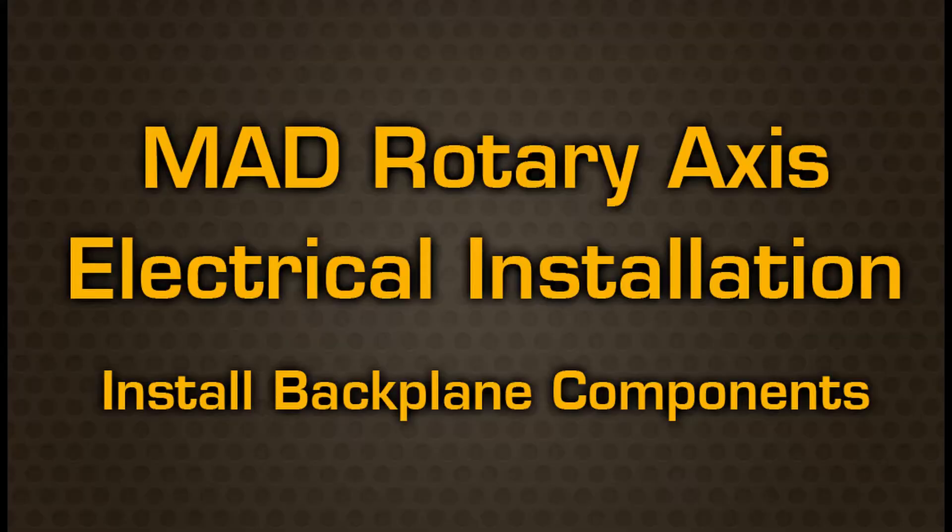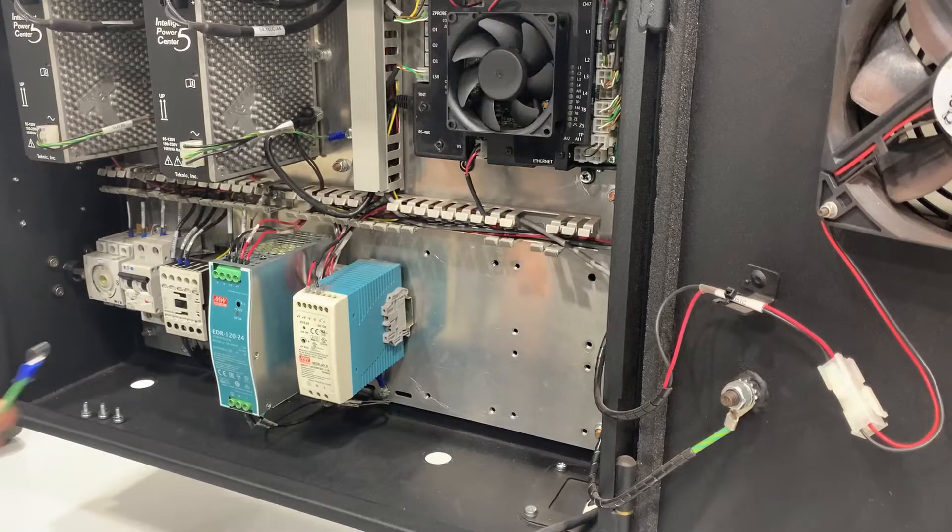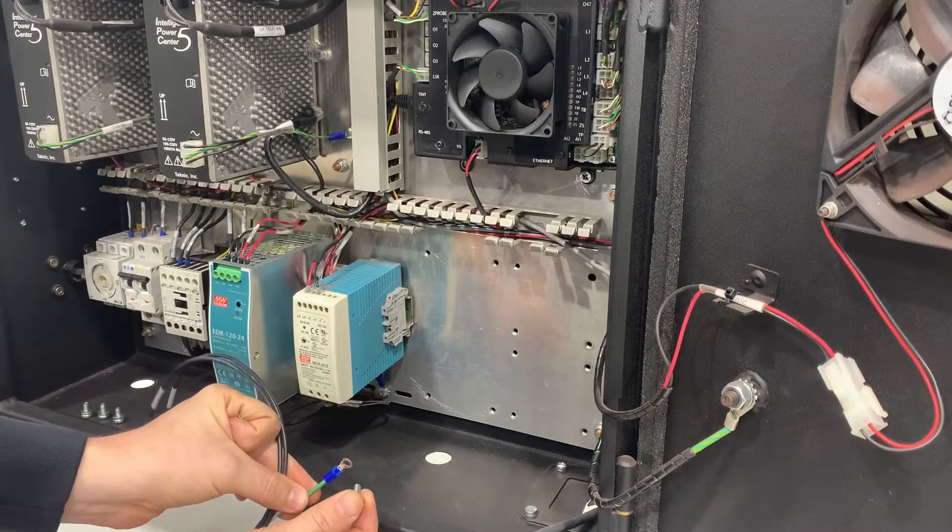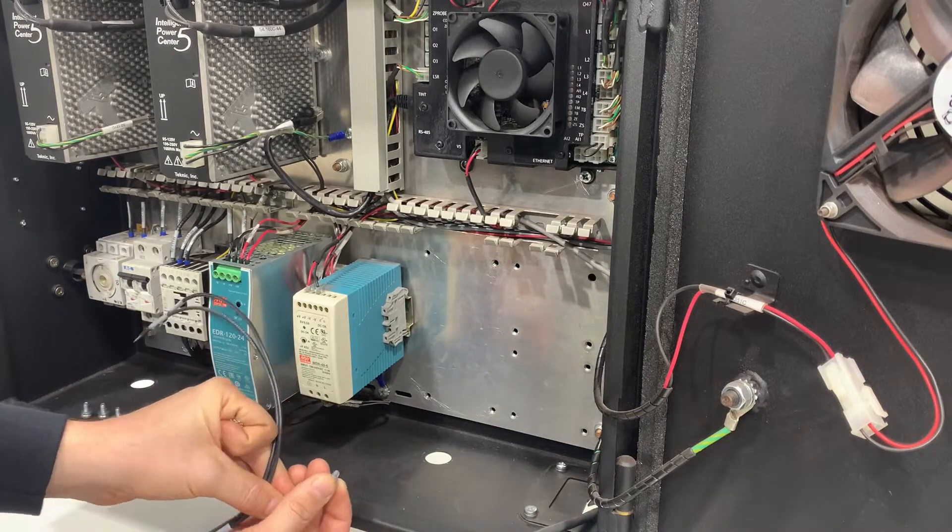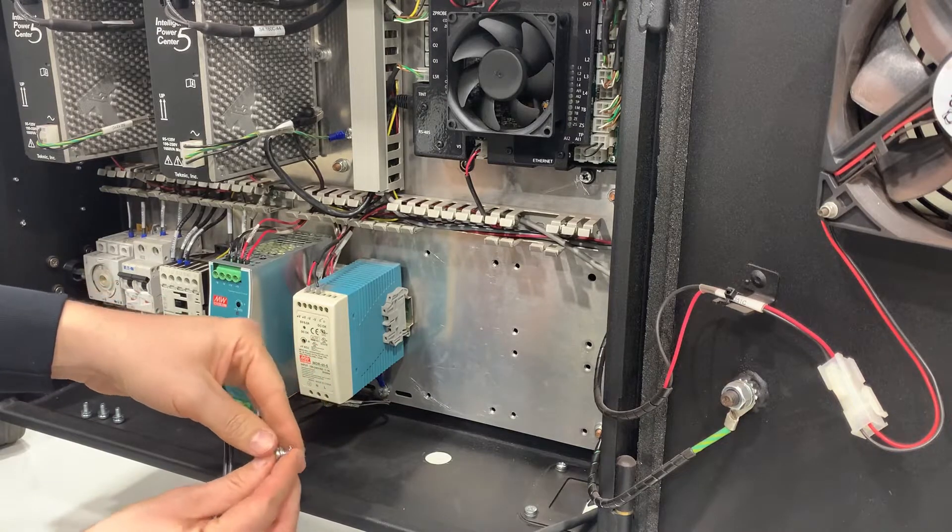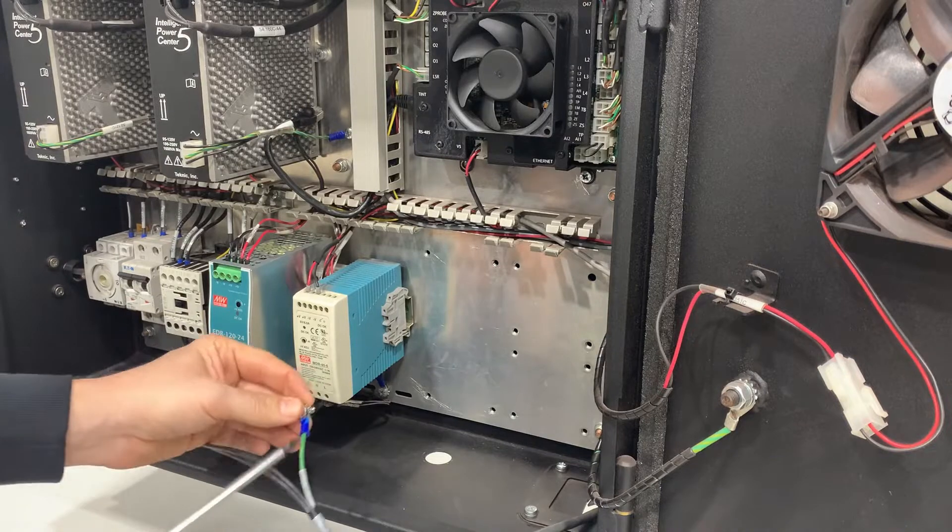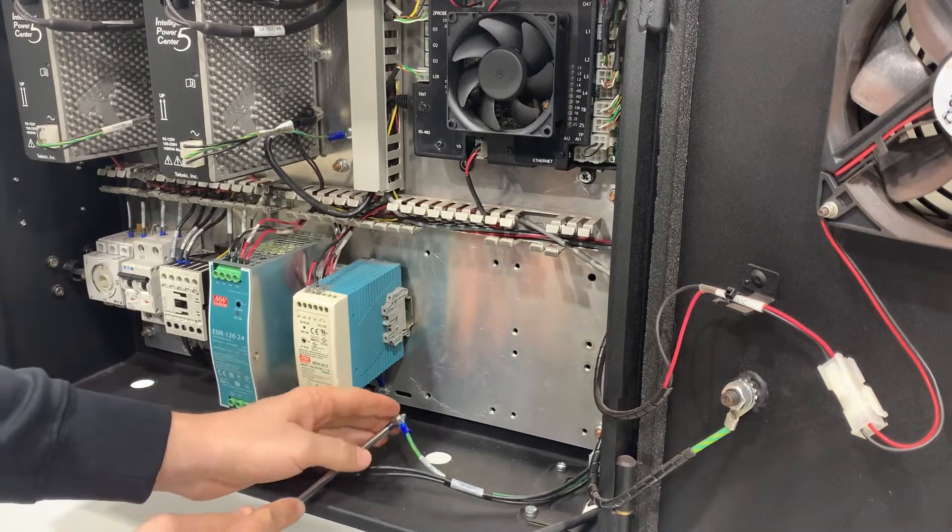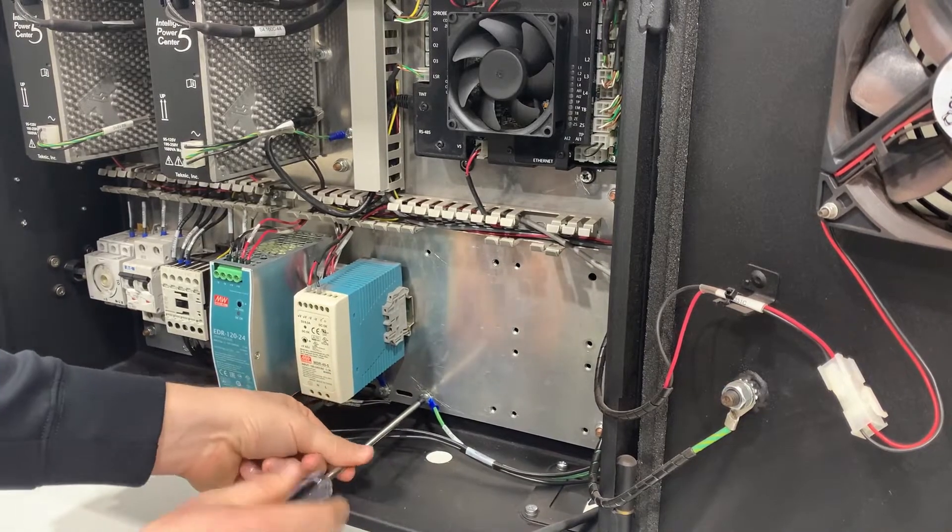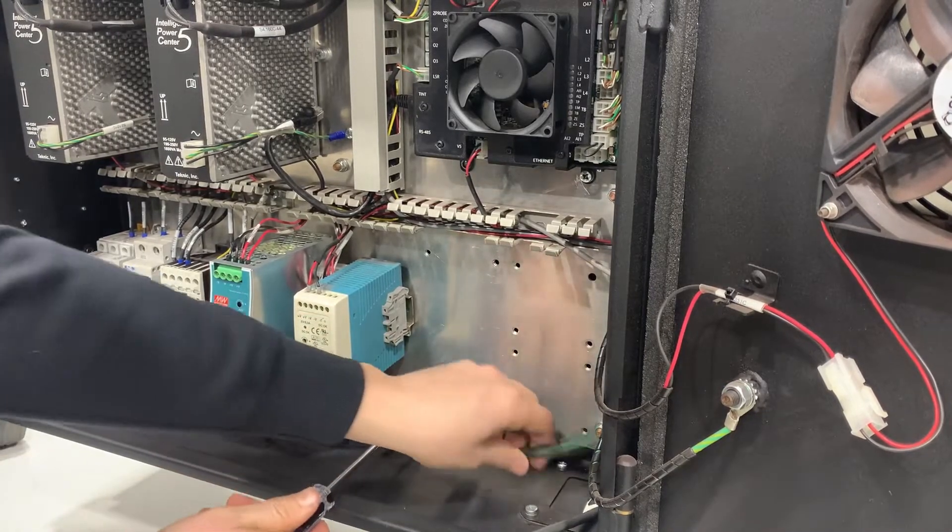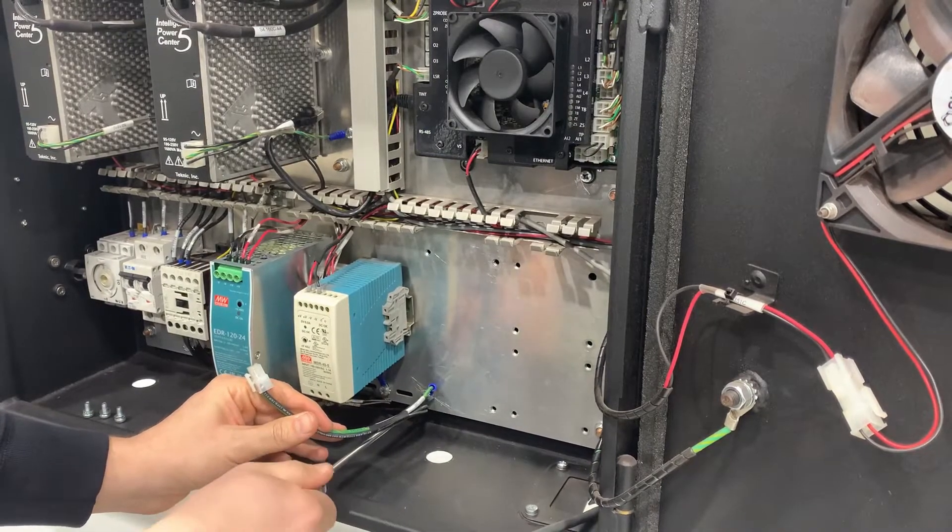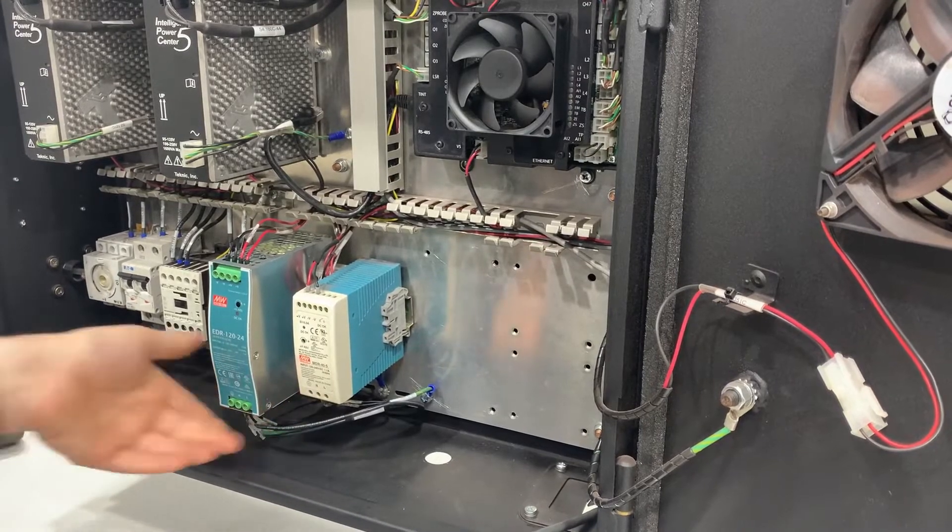Now that all the preparation work is done, we can install the components into the control panel. First, install the bonding ring terminal of the AC power end cable supplied in the kit using an M5 pan head bolt, washer, and star washer. This is installed into the lower left clinch nut on the back plane that is exposed. Pull the connector out of the way to the left so that we have room to install the IPC power supply.